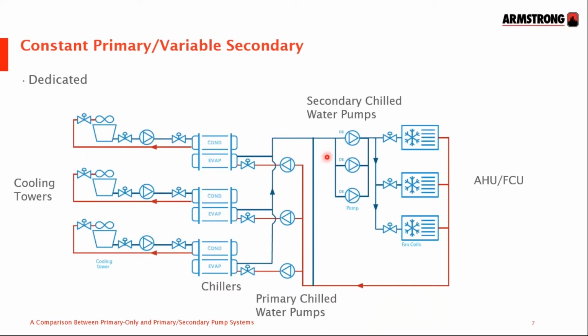The second set of pumps is the secondary chill water pumps. They will be taking water from the mixing header, from the chiller, and pumping through the system, through the control valves here, which are controlled by the building automation system, and they're controlling the flow through into these air handling units, which are taking the cold water and then with fans behind them are pushing cooler air into the zones. And then the water going through the coils in the air handling units picks up the heat and returns back to the chillers at a higher temperature.